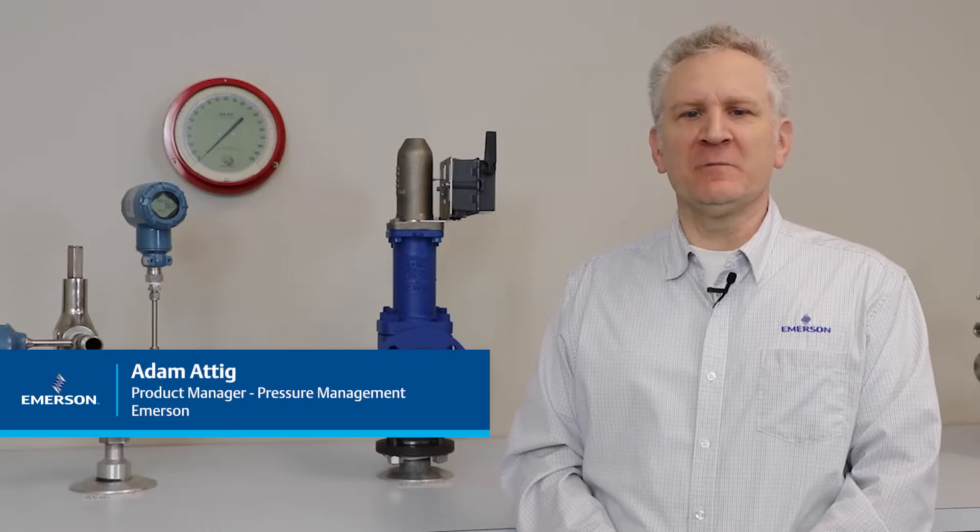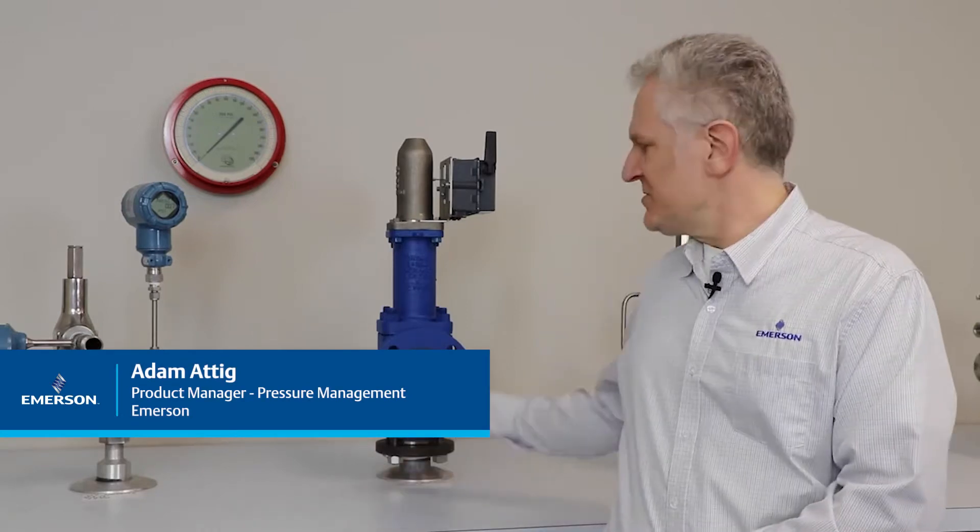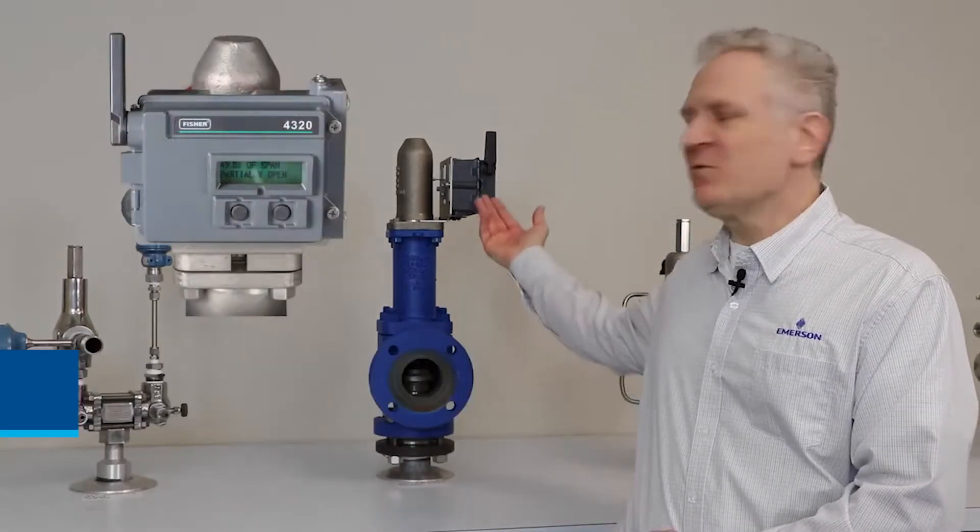The last example of a monitor PRV we will discuss is the Crosby J-Series with the Fisher 4320 position monitor. The Fisher position monitor is a linkage-less and easy-to-install design that is magnetically coupled to the valve trim. The monitor provides the position of the valve trim indicating the valve is lifted and an overpressure event has occurred.